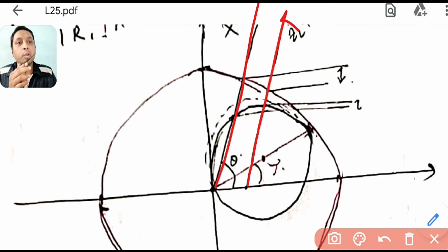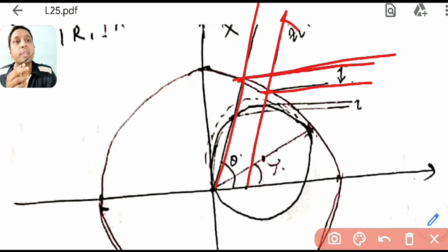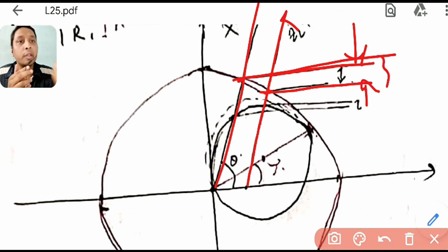If it is shifted horizontally, you can see the SIR was measuring this much, and now it will be measuring only up to this. So the SIR is missing this. This is the underreach of the simple impedance relay. In the case of the Mho relay, it was measuring this, and now it will be measuring a little bit higher. There is no underreach here, though my drawing is not perfect, but you can see it is very negligible. In fact, it is going overreach here, not underreach. So the underreach in the Mho relay, in this case, will be less for a resistive fault.